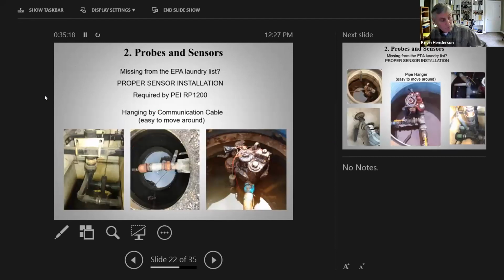So the other part about probes and sensors that's kind of missing from the EPA laundry list, if you will, is verifying that they are installed correctly. So RP 1200 requires you to verify proper installation as part of your functionality test. And you'd be amazed at some of the ways these sensors are installed or not installed or just haphazardly thrown around, because all kinds of crazy stuff happens. Many times you'll see them just hanging by the wire itself, which is not unusual. They're not attempted to be mounted anywhere. There's no effort to really secure them in any way. They're just hanging by the wire or leaned up against something. That's very typical.